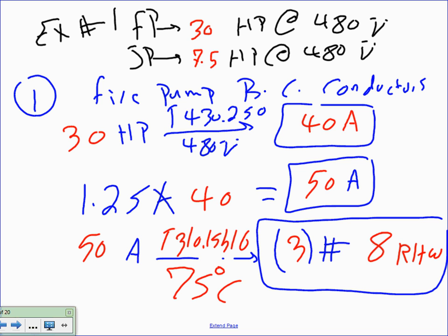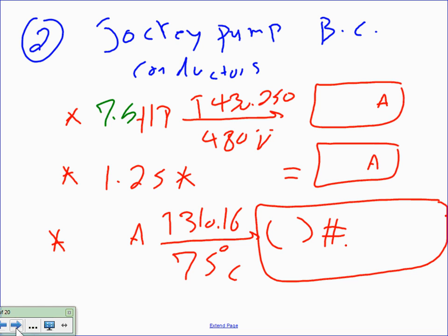Can I do THHN on it? Yep, if you put it in an EMT conduit. Yeah, if you're going to be, I mean, THHW, underground, buried, then no problem too. Any question, guys, about the branch circuit? So, on the test, when you have the test, I would like you to emphasize how many of them, which step, with how many, and what installation you're using. No neutral.